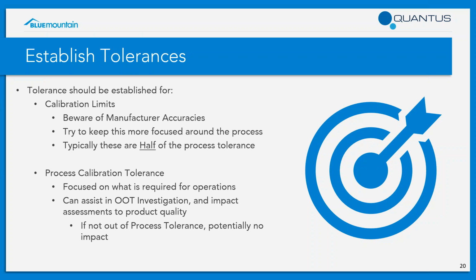And then talking about process tolerances, this is another difficult task that not a lot of customers can employ. However, if you are able to establish this, we're going to want to talk about keeping them mainly around GMP critical devices, because it's going to reduce the overall population that you have to evaluate, and it's going to really help you in OOT investigations. In general, if the UUT, or the unit under test, was outside of the calibration tolerance but not outside of that defined process tolerance, you're going to have a lot more confidence that there was no impact to your product during that service.